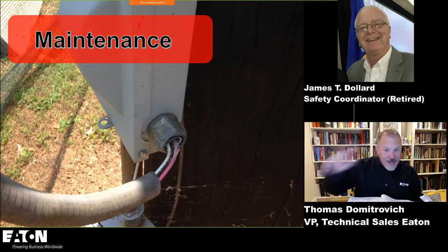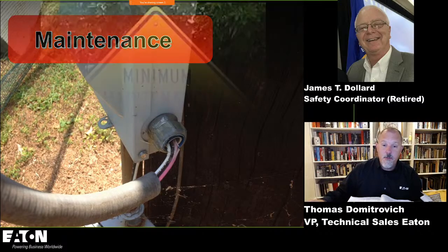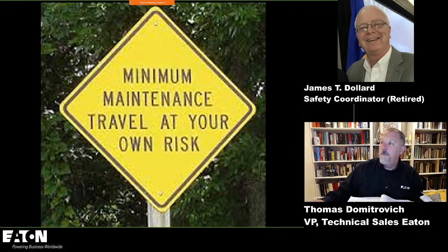And I took that photo as well. Maintenance is another area of concern when it comes to electrical safety, and 70B, as in Bob, is our reference for that. And we travel at our own risk whenever we get into a maintenance perspective. Now, the National Electrical Code, Jim, does have some requirements for maintenance in Article 700. You're on panel 13. And yeah, 700 and a few others.